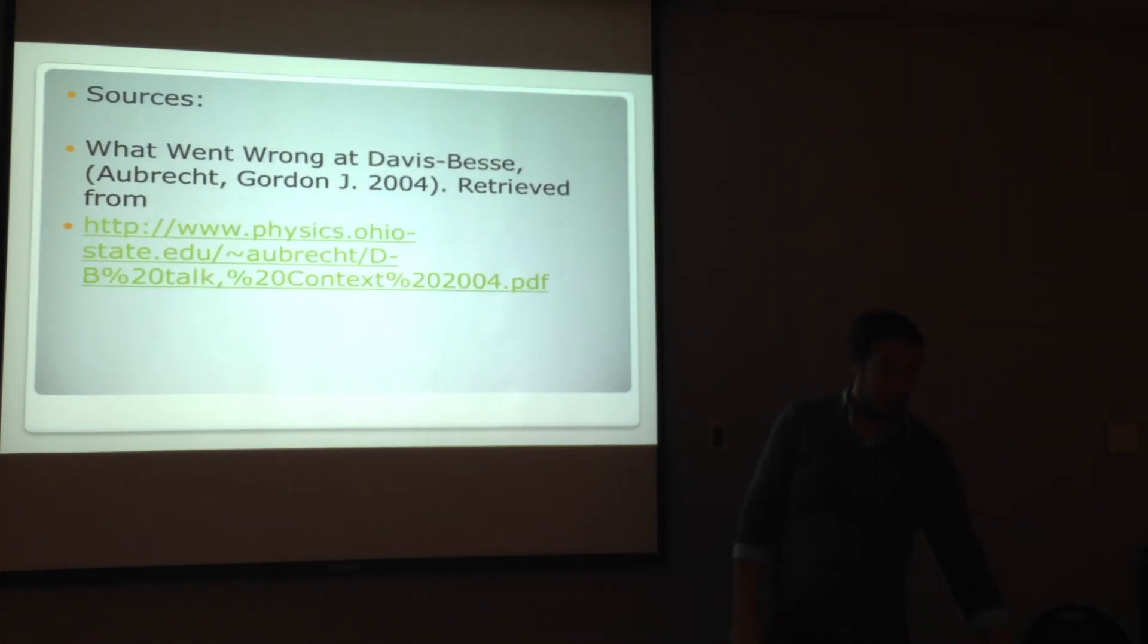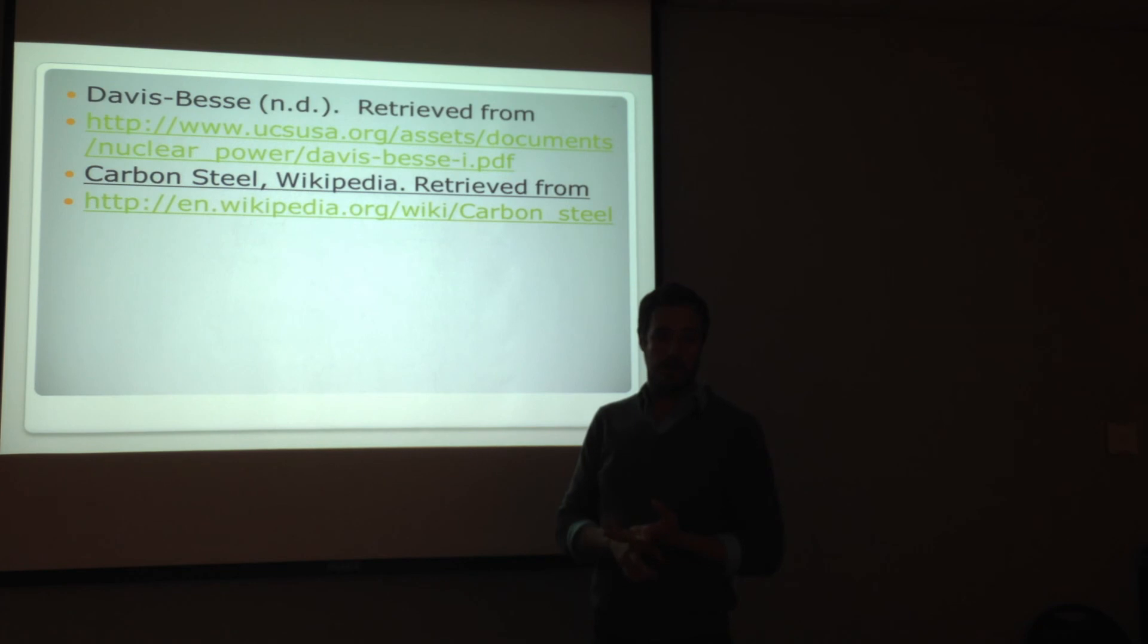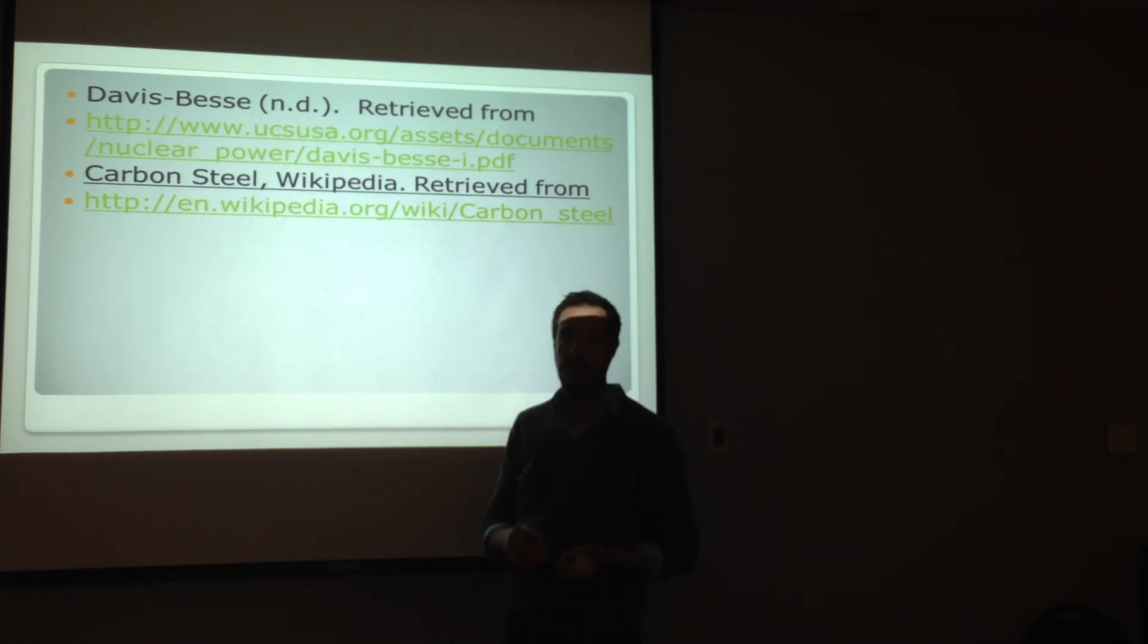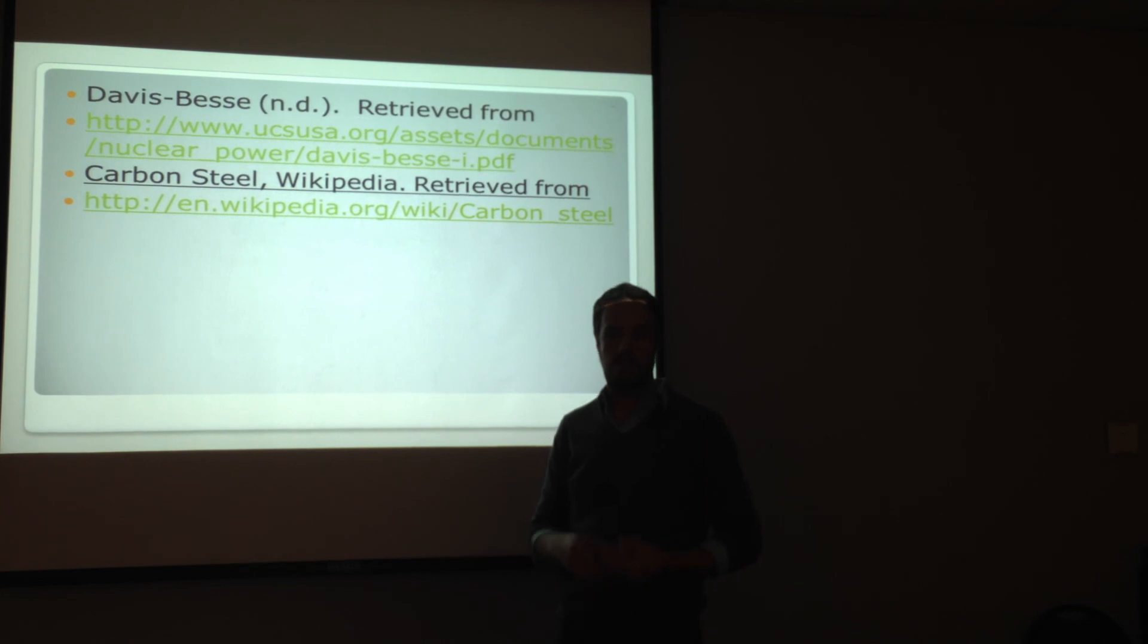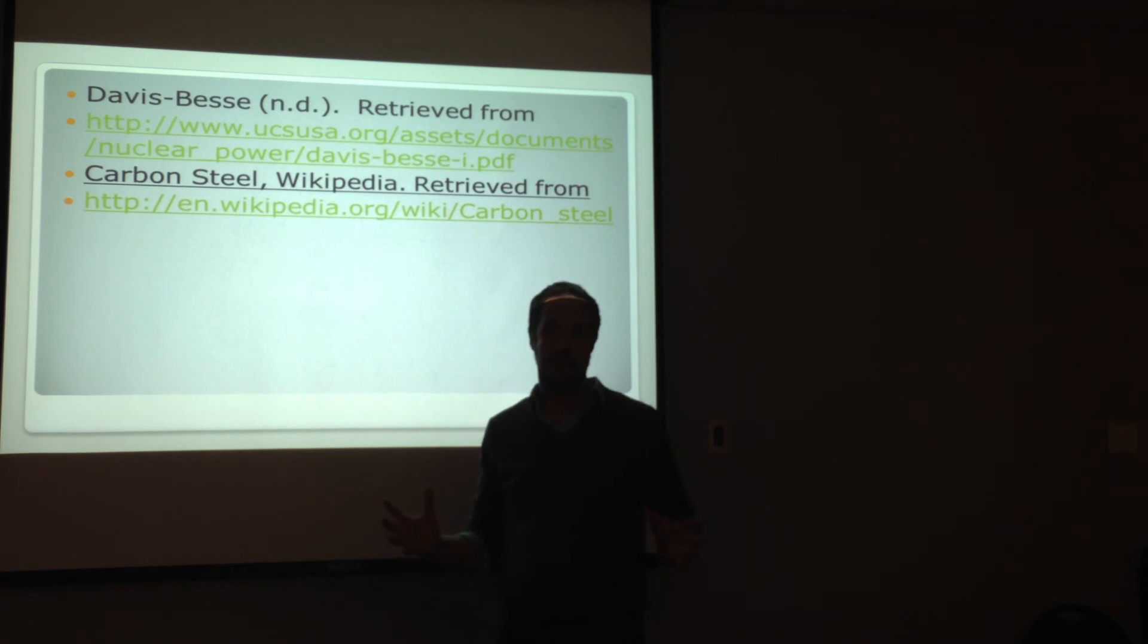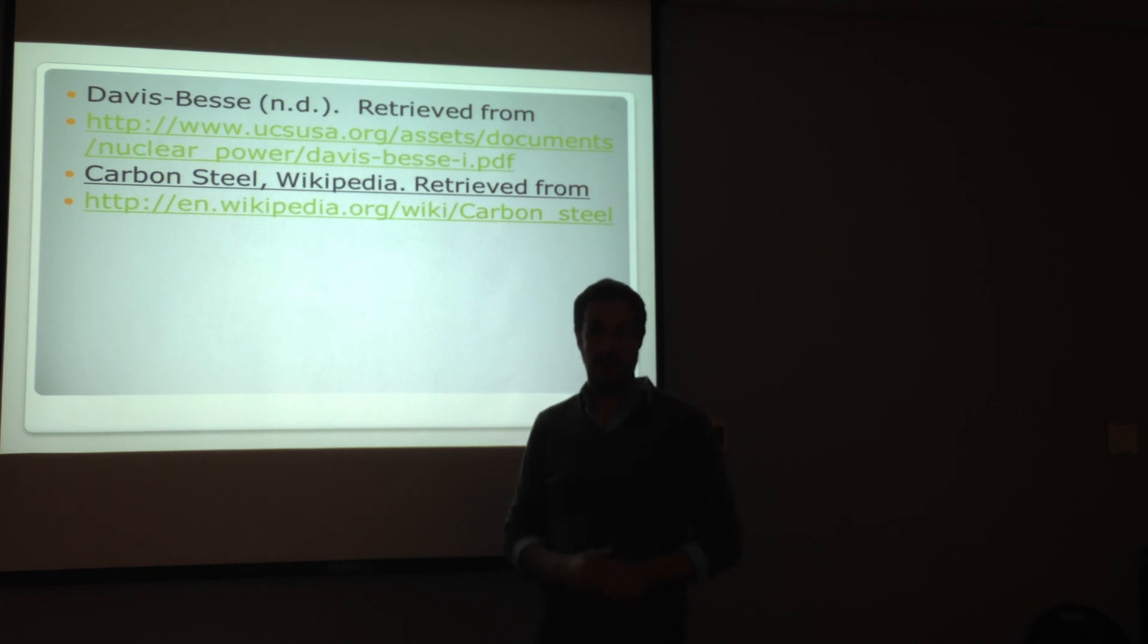And, also, what was discovered was it's great to have a strong reliance on a strong program such as the boric acid corrosion control program. But, unless you're using your mind and thinking outside the box when something doesn't seem right, like the large amounts of boric acid deposits they were finding in the containment air cooler systems and in the filters, and knowing that there weren't any primary leaks from the usual suspects, nobody thought, well, where might this be coming from and why are we seeing this? So, a lot of things were learned from this. Hopefully, you learned something.